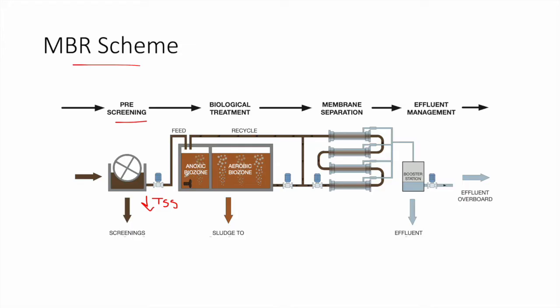Then we have the anoxic treatment — denitrification without oxygen, in anaerobic conditions. Then we have the aerobic treatment, where diffusers inject air into the wastewater. Then we have the MBR treatment — the membrane separation. We are seeing here tubular MBR; we will see later that there are other types of MBR filters. This can be the final stage before water reuse or disposal, or we can use an optional disinfection step, depending on local regulations and whether you want to reuse the water or just dispose of it.